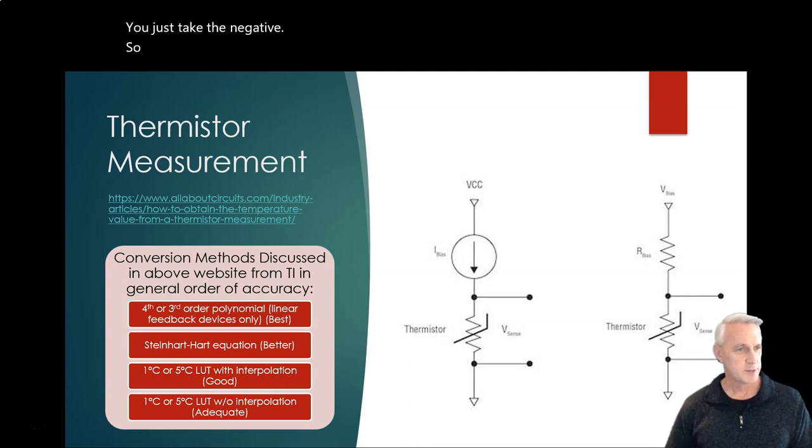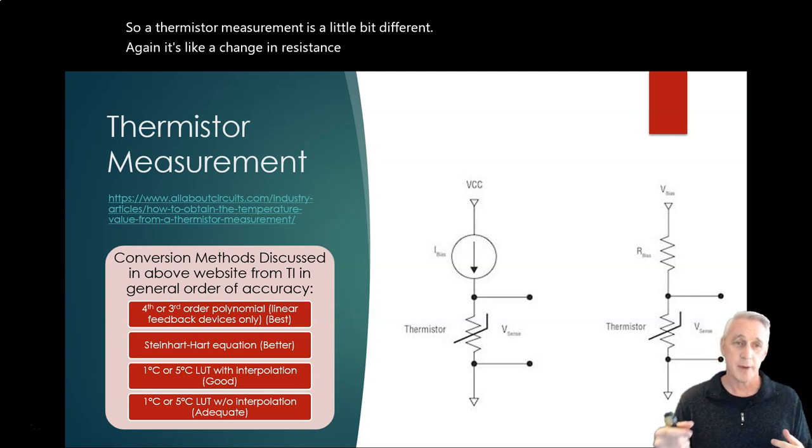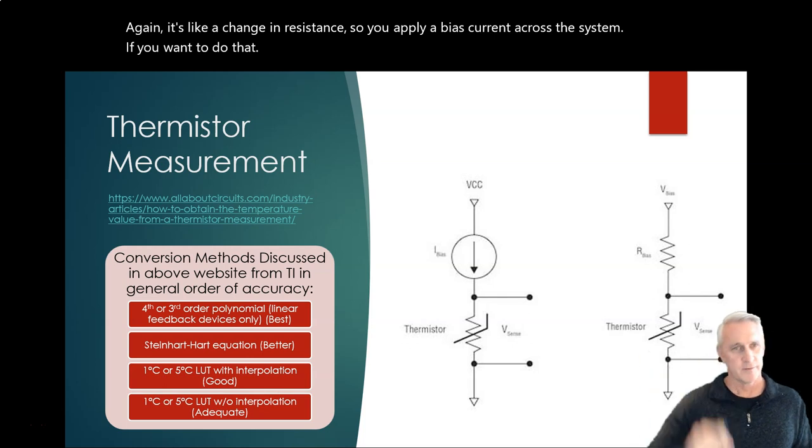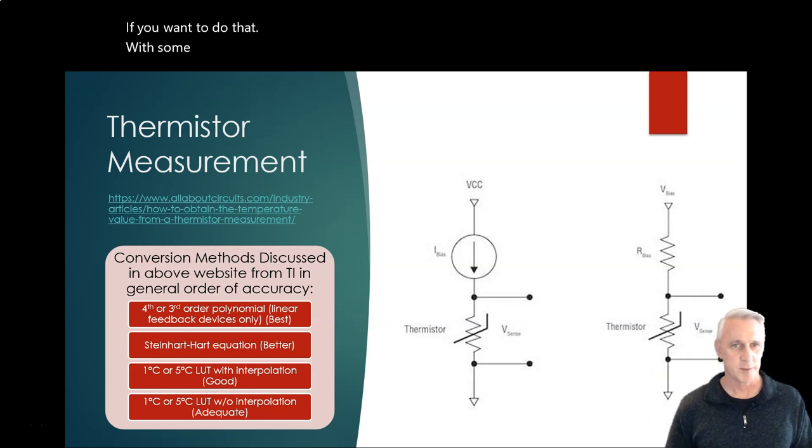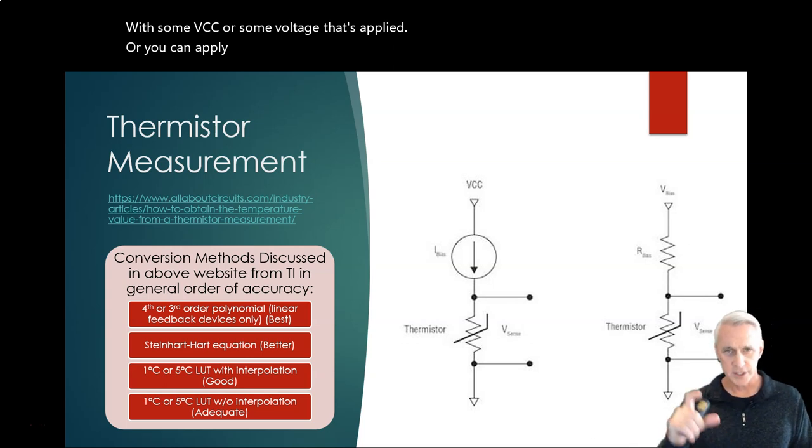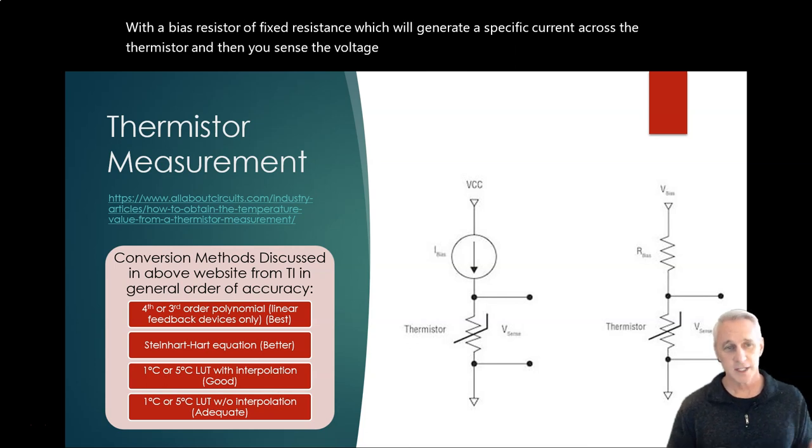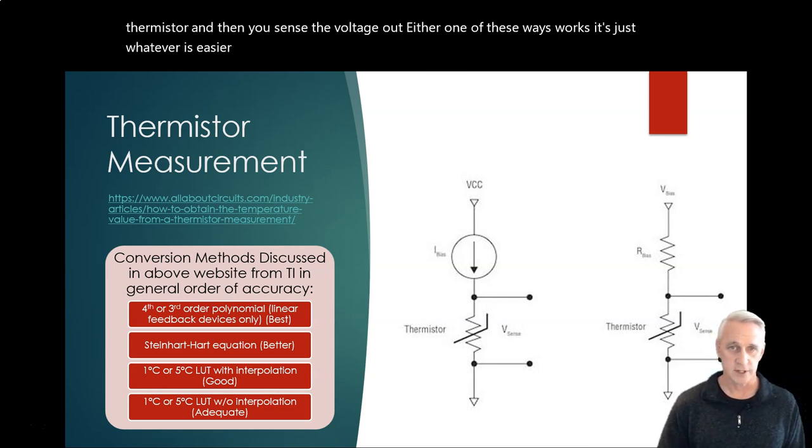Thermistor measurement is a little bit different. It's like a change in resistance, so you apply a bias current across the system with some VCC or some voltage that's applied. Or you can apply a bias voltage with a bias resistor, a fixed resistance, which will generate a specific current across the thermistor, and then you sense the voltage out. Either one of these ways works - it's just whatever is easier for the application.